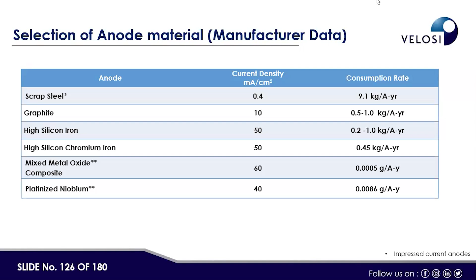So how can we measure whether your anode can work in this environment, and what your transformer rectifier unit capacity should be, what potential, voltage, and current you need? For that, we should know the soil resistivity, which gives an indication of how corrosive the soil is.